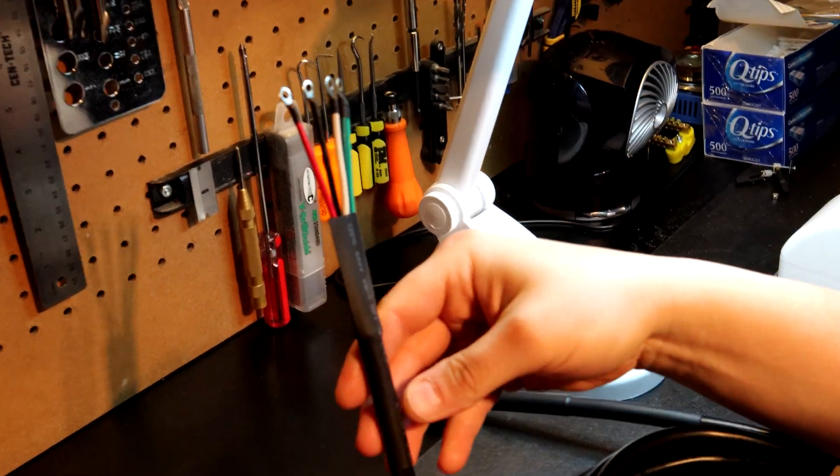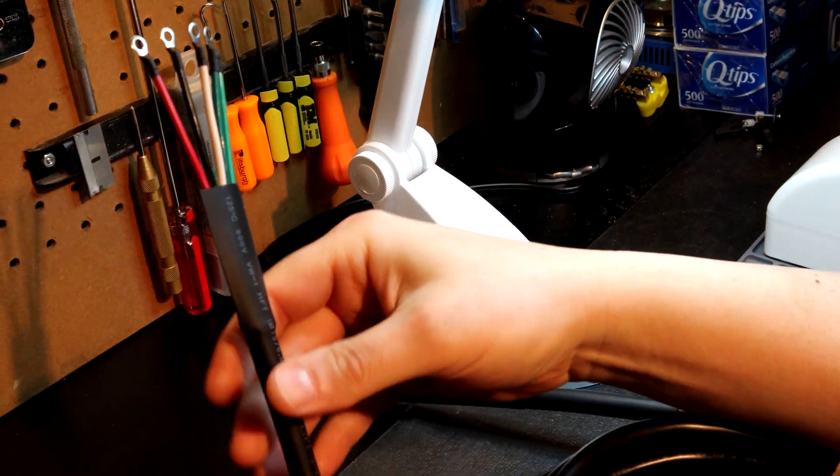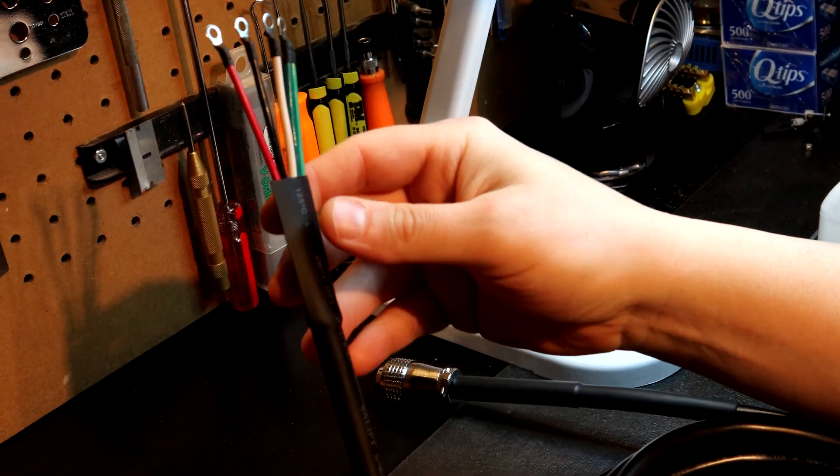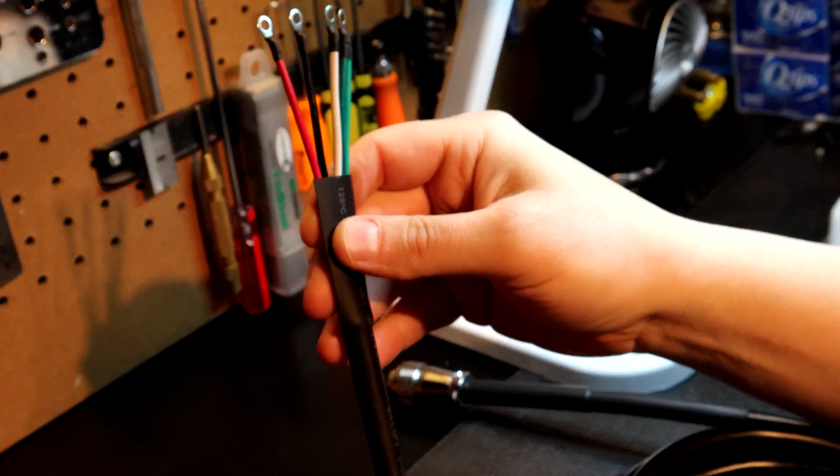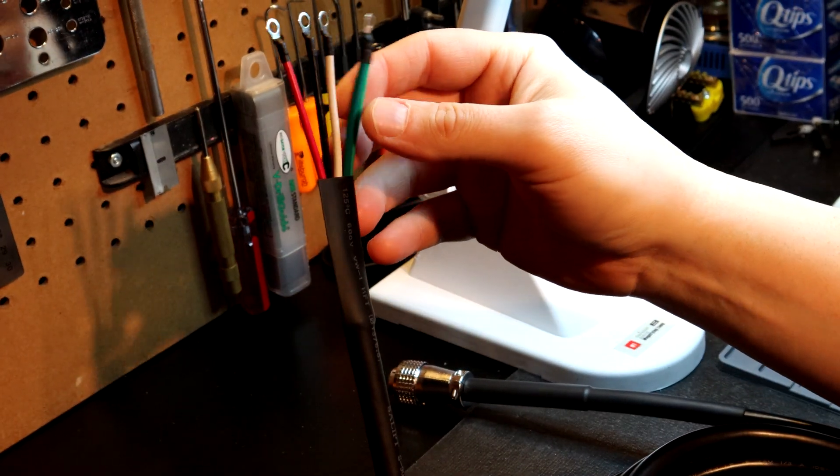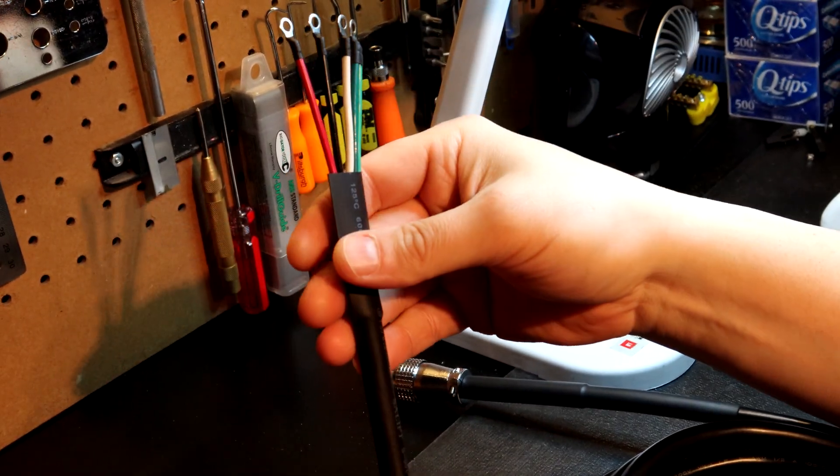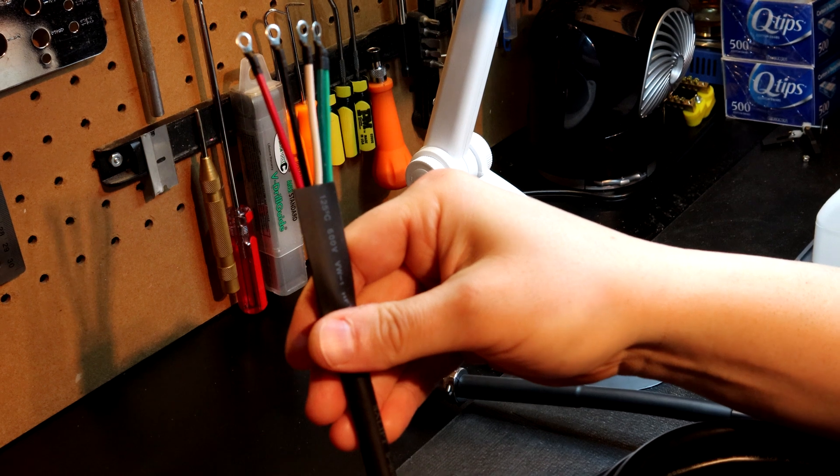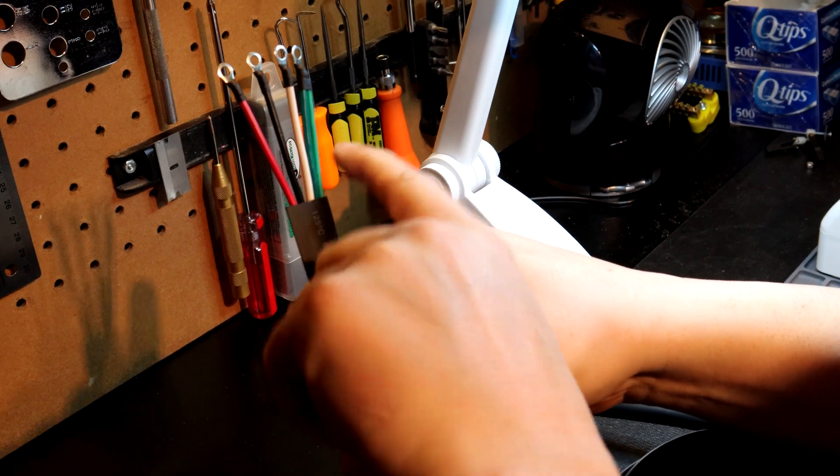On the opposite side where the boot is, I really don't care about the thickness on the shrink. You actually want it to be a little thinner because we want to be able to manipulate our leads once it enters the VFD.